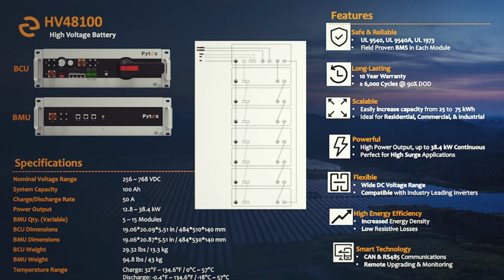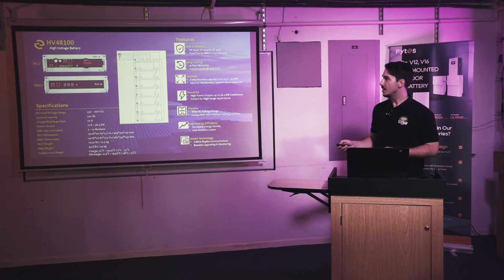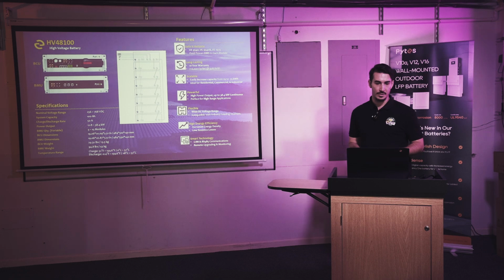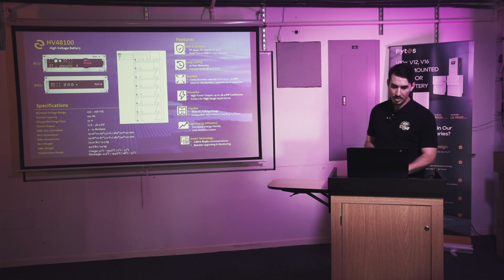They all connect in series and then land on your BCU, which is the master BMS. Actually, there is a contactor BMS in the BCU, and each module has its own BMS too. As you can see here, this is your user interface — this is where we're turning it off and on, your inverter cables, your comms, communication protocol, dip switches, and everything like that.